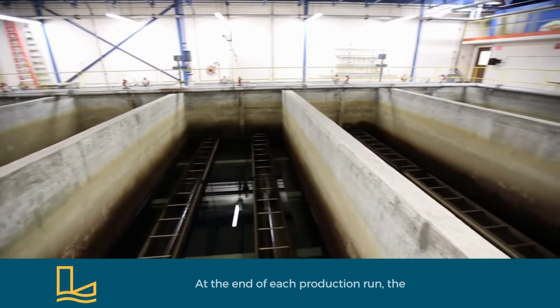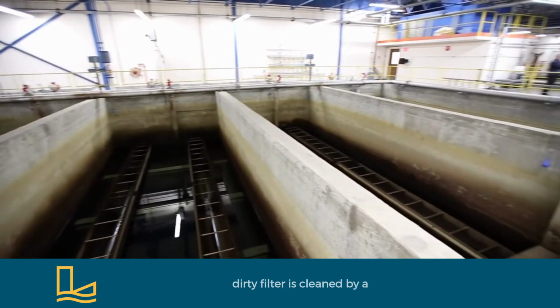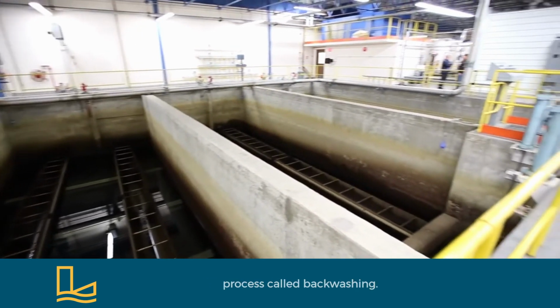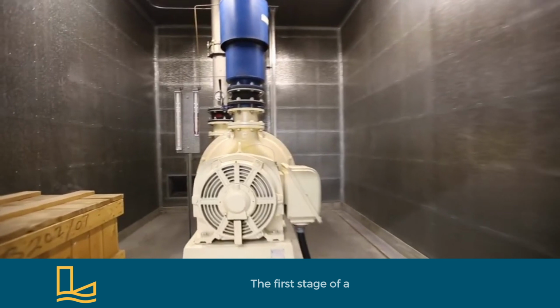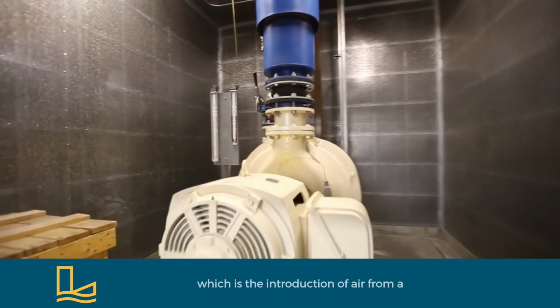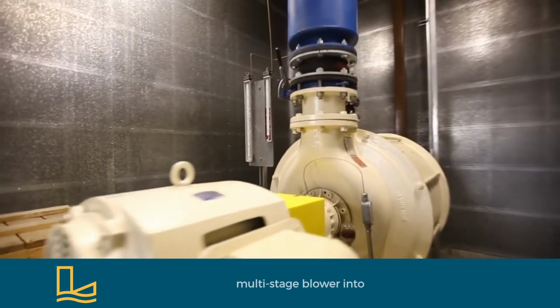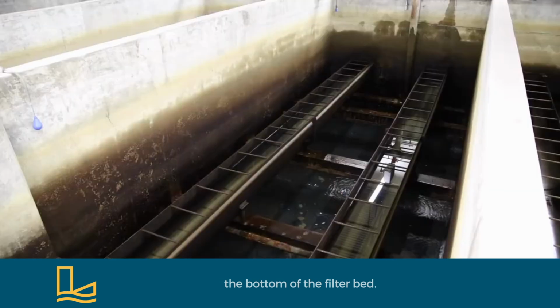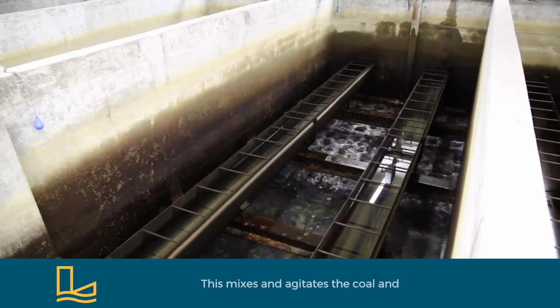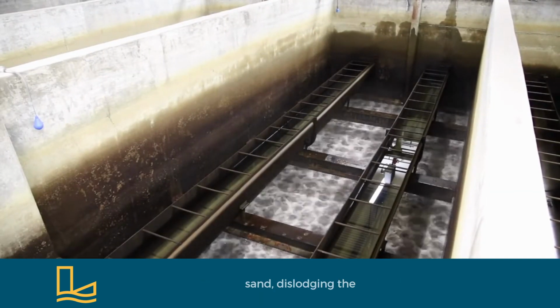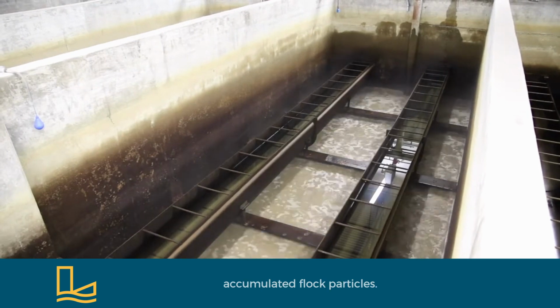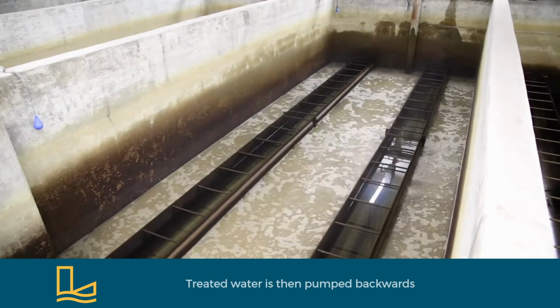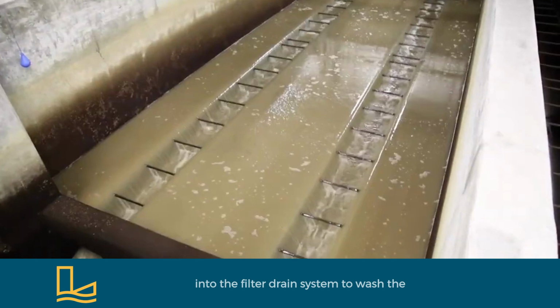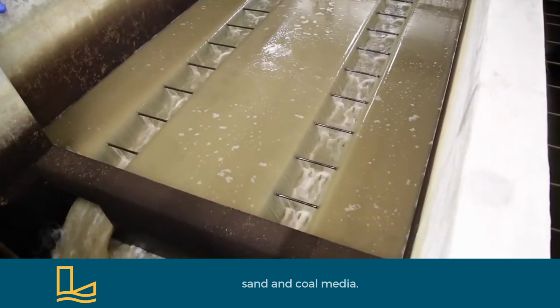At the end of each production run, the dirty filter is cleaned by a process called backwashing. The first stage of a backwash is the air scour, which is the introduction of air from a multi-stage blower into the bottom of the filter bed. This mixes and agitates the coal and sand, dislodging the accumulated floc particles. Treated water is then pumped backwards into the filter drain system to wash the sand and coal media.